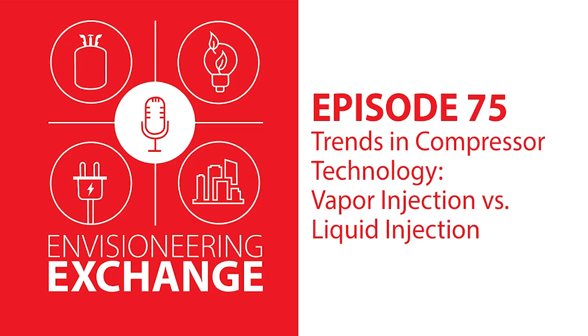I always get nervous when you talk about injecting liquid into a compression area, right? Liquid doesn't like to compress very well. That always made me nervous, so it's good to see the vapor one coming along. But you touched on it, right? With liquid injection we're not really optimizing the efficiency and the operating envelope. Liquid injection is more about protection, or we do extend the operating envelope a bit because we can help bring down discharge temperatures. But it's really vapor injection that has allowed us to increase the operating envelope and the range the systems can work within. Is that right?